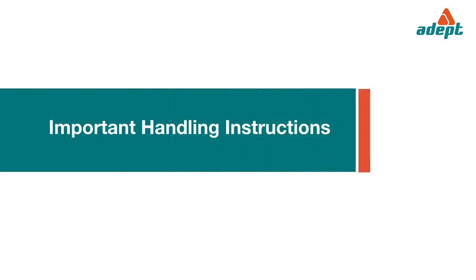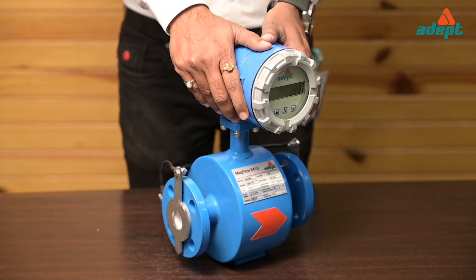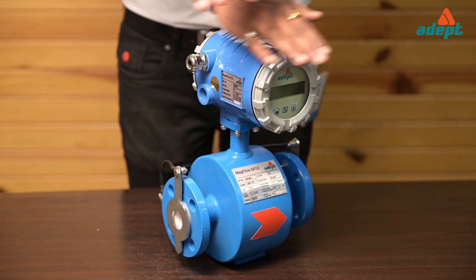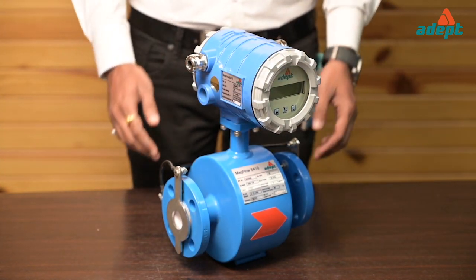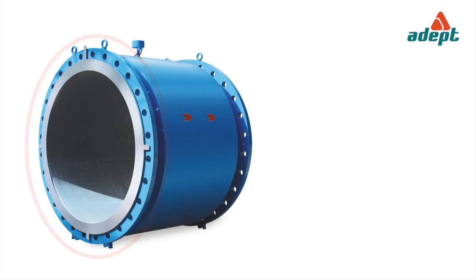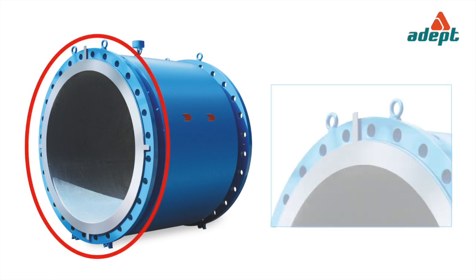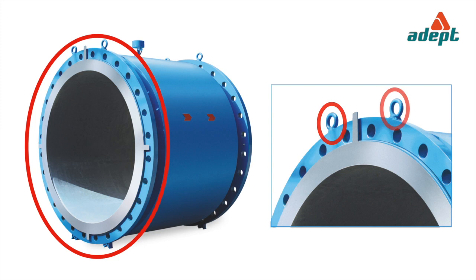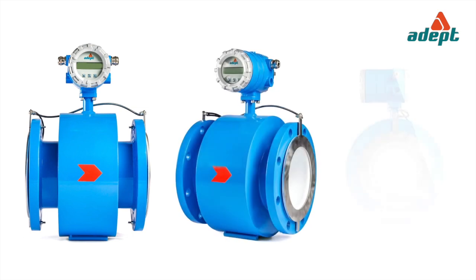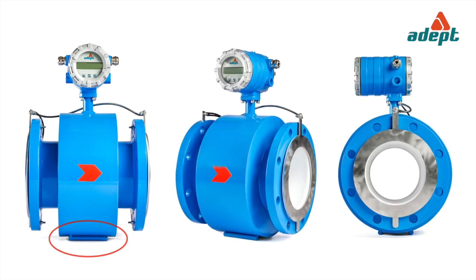Important handling instructions. Do not lift the flow meter by the top mounted transmitter in case of an integral type flow meter. Do not lift the flow tube by its casing. Always lift the flow meter of size DN200 and above using the eye bolts. Always rest the flow meter only in its upright position on the pedestals provided and not on its casing.